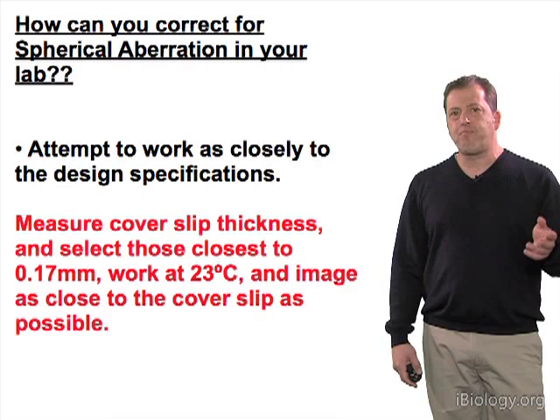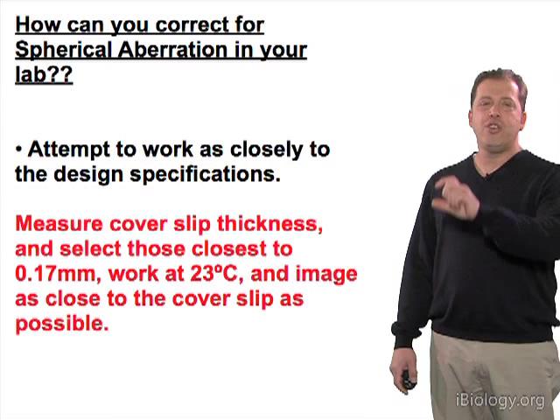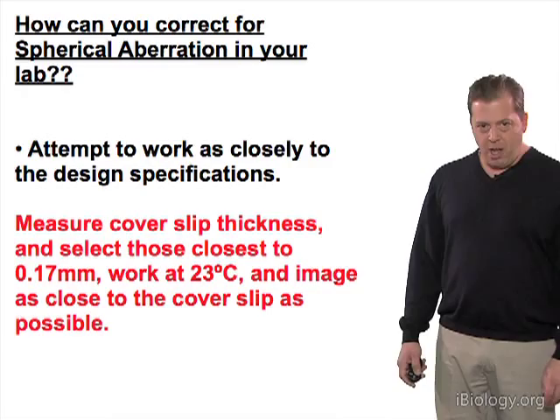Another thing you can do is measure your cover slips to achieve the design criteria of 170 microns thickness. You'll use a micrometer to measure them and throw out ones that are too far outside the criteria needed to maintain the proper optical path length.